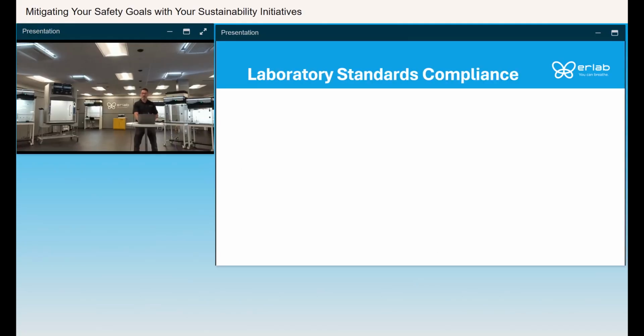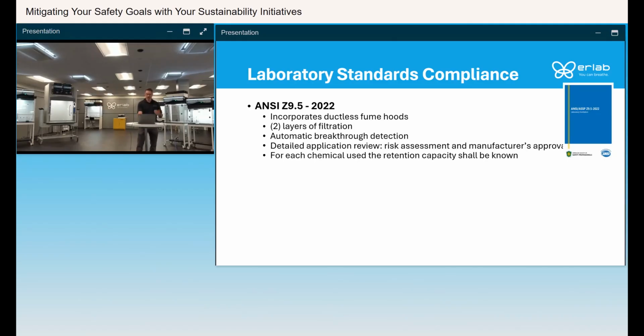Now, how do we comply with the current laboratory standards? Well, ANSI Z9.5, the 2022 version, fully incorporates ductless fume hoods, and you're going to see a common theme here. 2 layers of filtration, so that's having those backup safety filters. Automatic breakthrough detection, having those solvent or acid sensors on the hood. Detailed application review, that's that chemical questionnaire, filling it out. And then for each chemical used, retention capacity shall be known. So it's all that testing we've done with that chemical listing. We're able to give that to you.